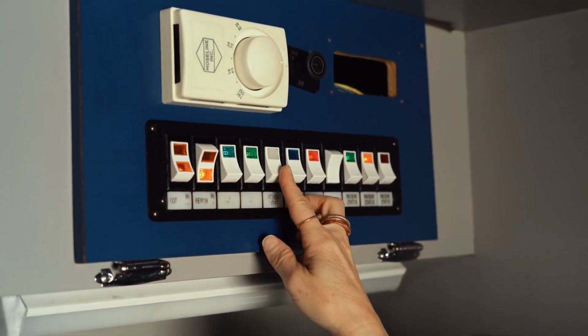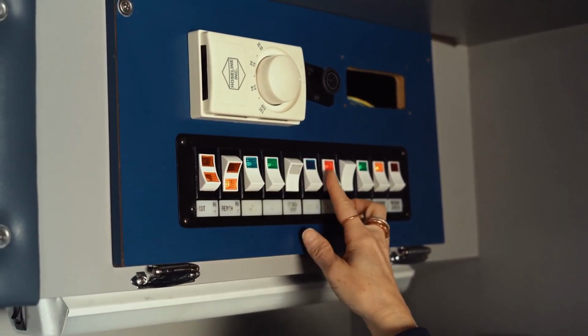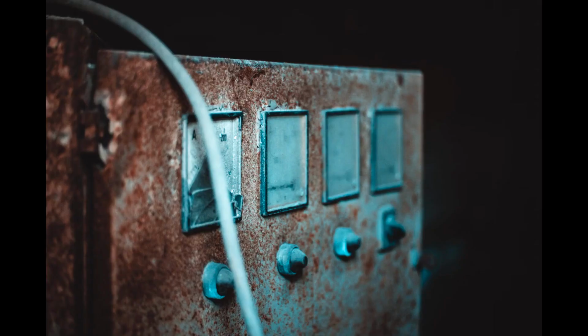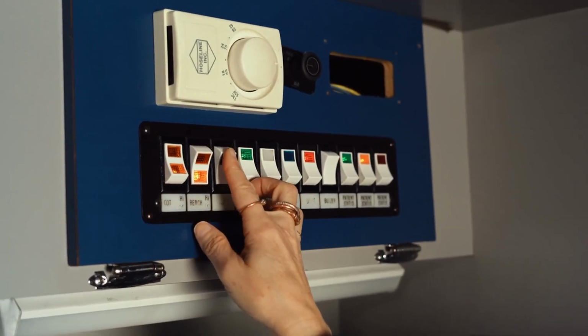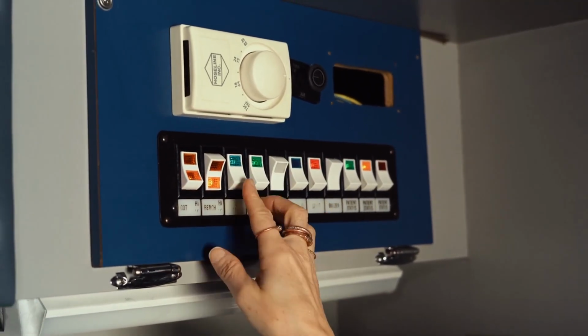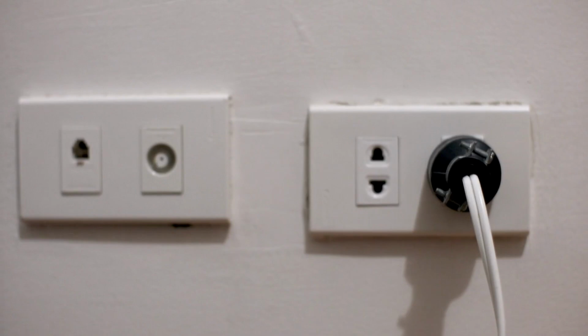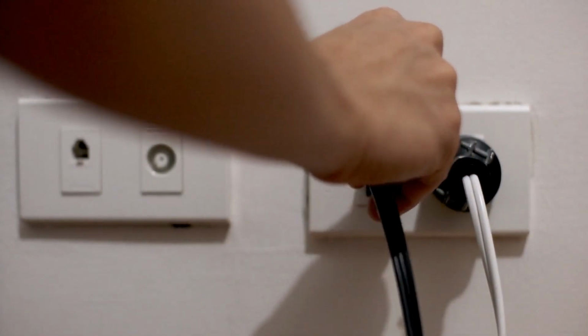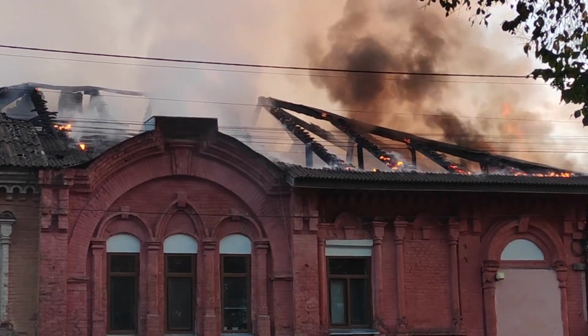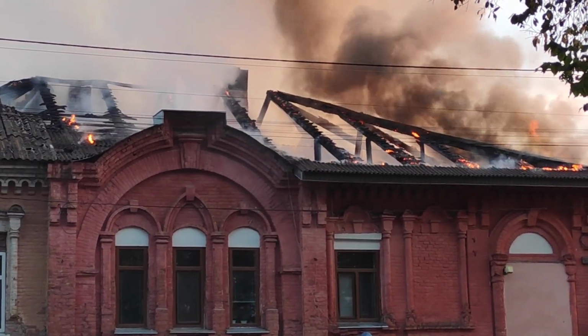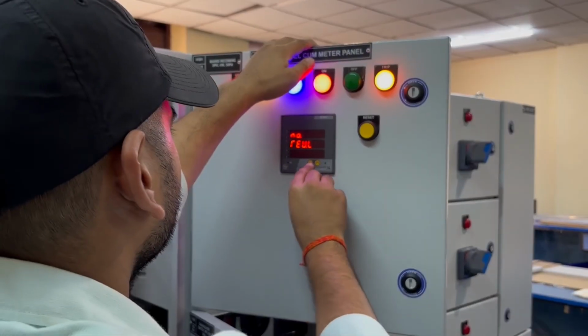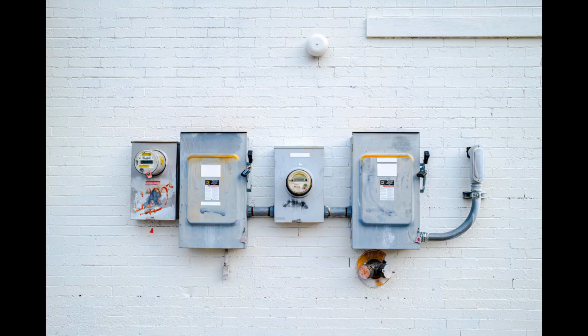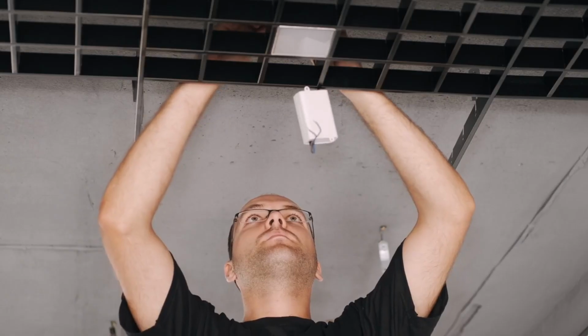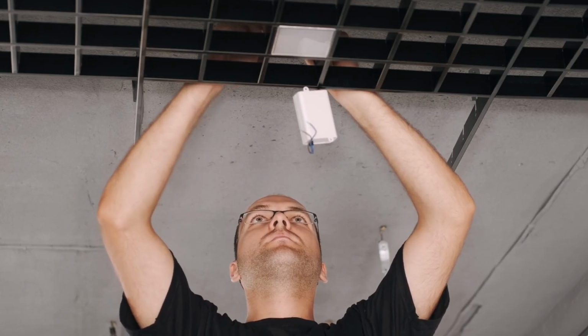And then there's Federal Pacific. Look, I'm going to be direct here. If you're buying a home with a Federal Pacific Stab-Lok panel, get it replaced. Period. These panels have a documented history of breakers that fail to trip under overload conditions. That's the entire point of a breaker. It's supposed to cut power when something goes wrong. When it doesn't, the wiring overheats, and you have a fire. The cost to replace a panel runs somewhere between $1,500 and $4,000, depending on your location and the scope of work. That is money worth spending. Don't let anyone talk you out of it.